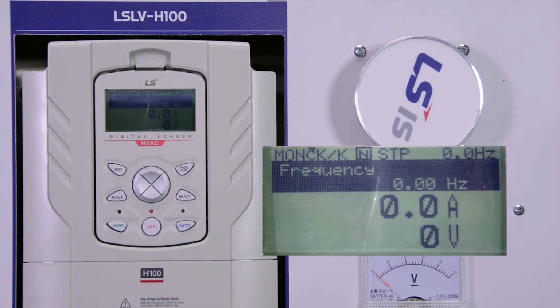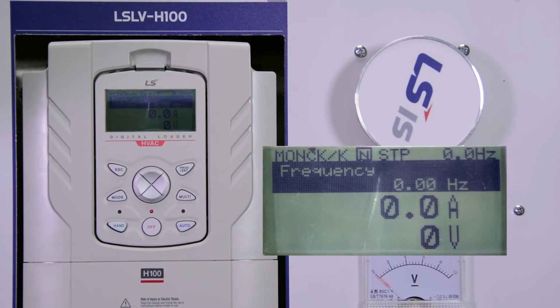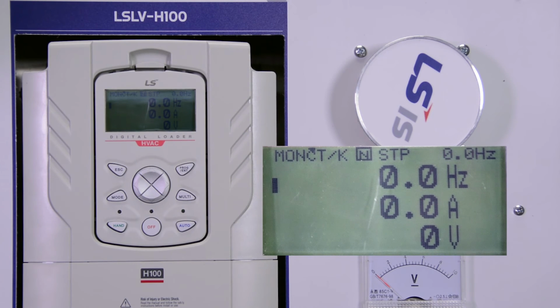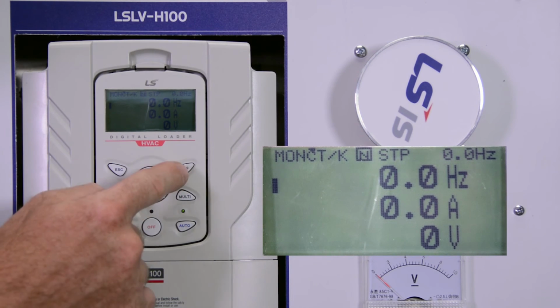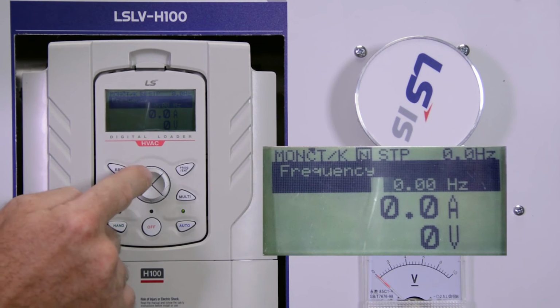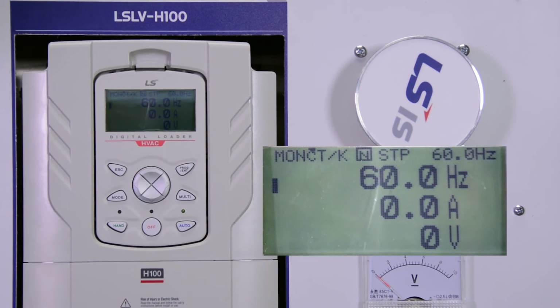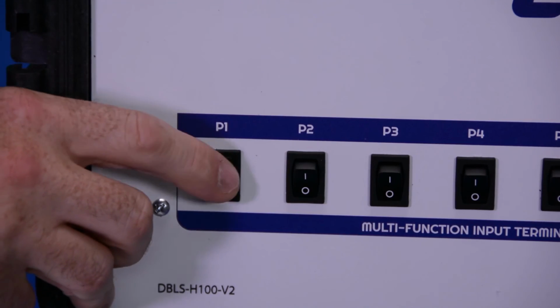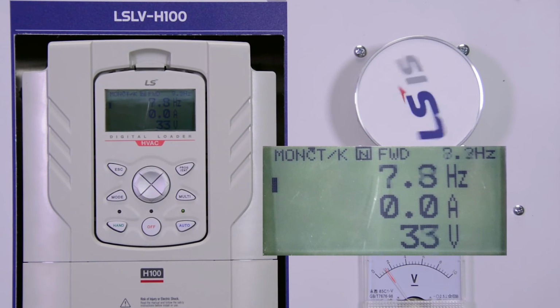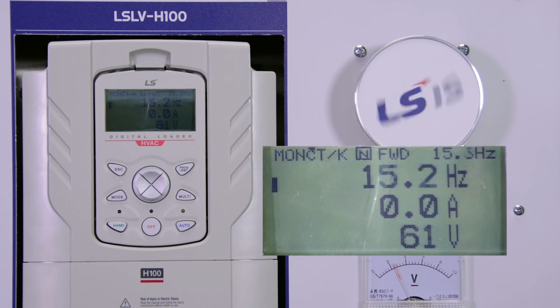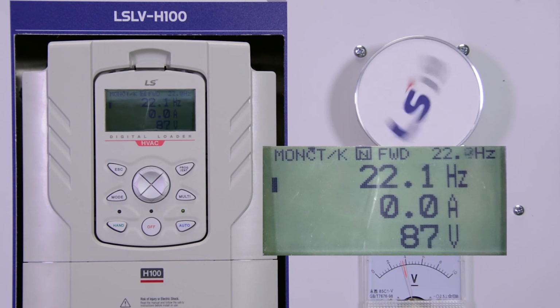And that is the basic setup for this. Next, we will start the motor. In order to use the H100, you have to use the drive in the auto mode. So the auto button has to be pressed. So you press the auto button and the LED will flash until it gets the signal it needs to start the drive. Set the speed and turn the digital input on. And that's the basic setup for the H100.